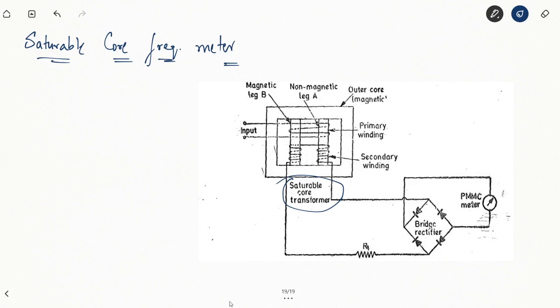This core assembly basically consists of three parts. You have the outer core, that's the magnetic material, and the outer core is of a larger cross-sectional area. This large area means no magnetic saturation. So the outer core is made up of the magnetic material, and it will not saturate because of the large cross-sectional area.